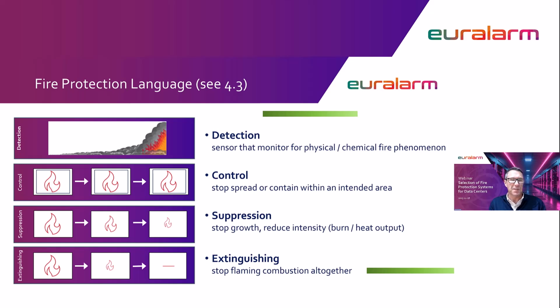Next, we have suppression. Think systems like water mist, effectively reducing the fire intensity. The suppression is a reduction in heat output, or you could say an increase in localized heat consumption, but that's reliant on the water mist getting to the seat of the fire. Noteworthy there, suppression systems typically have a minimum runtime, and that's to provide control and suppression until the fire and rescue service, the fire department or fire brigade, depending on your language, for them to arrive and get in, and for the firefighters to achieve final manual extinguishment.